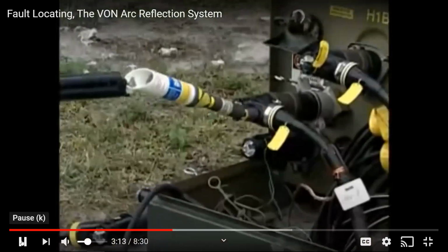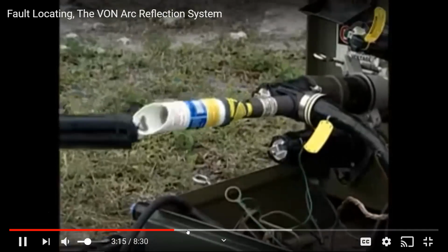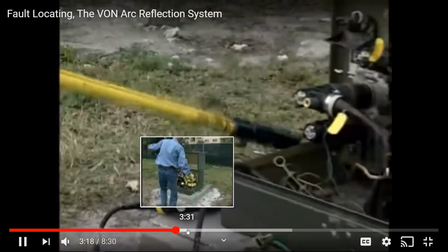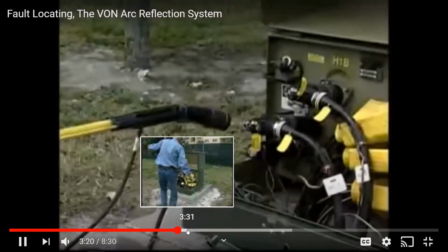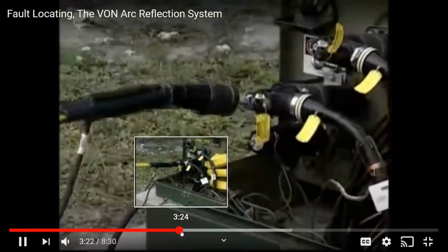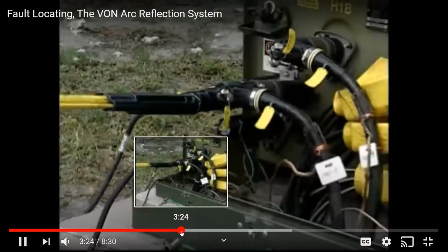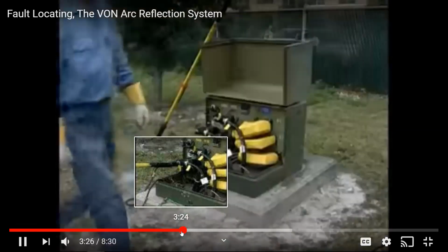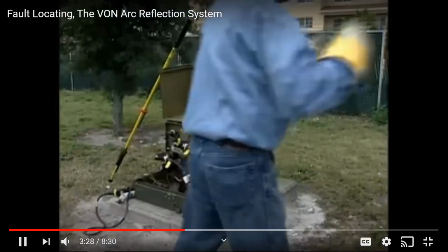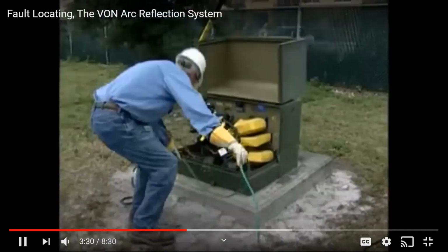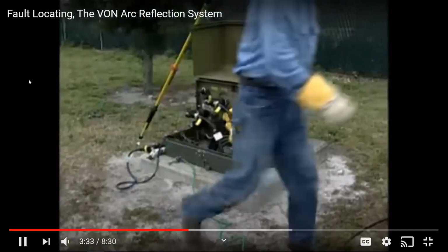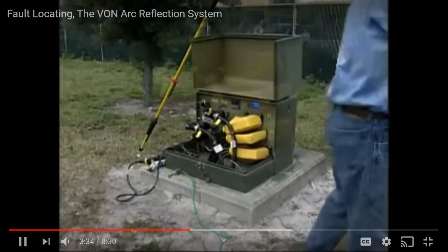Or detection device. Test the other side of the feed-through or test port to ensure the cable is de-energized. After you complete the testing, be sure to insert a grounding elbow in the feed-through. You're now ready to hook up the leads from the Von. One quick note, be sure the green safety case ground is uncoiled fully before beginning the hookup.